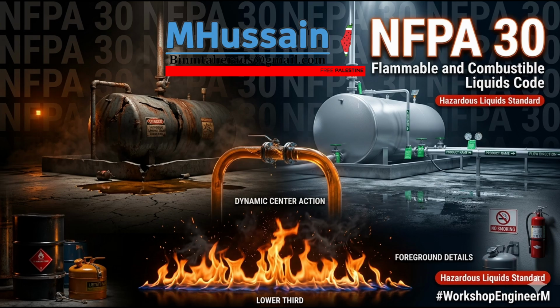Exactly. But the closed cup test, like the Pensky-Martens or the Tagliabue closed tester, you put the liquid in this sealed brass cup. Okay. And then you slowly, meticulously heat it up, maybe a couple of degrees a minute. And because it's sealed, those vapors get trapped in the tiny void space right above the liquid. So it creates a really concentrated vapor-air mixture. Right. Which perfectly mimics the worst-case scenario, like a steel drum baking in the sun inside some unair-conditioned warehouse. That is exactly the point. It simulates confined hazard conditions.